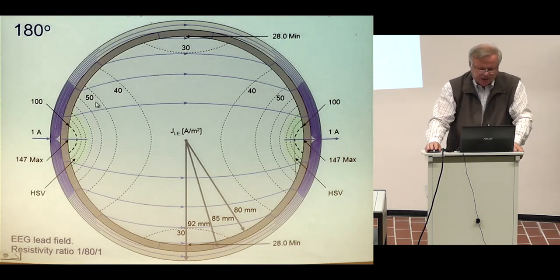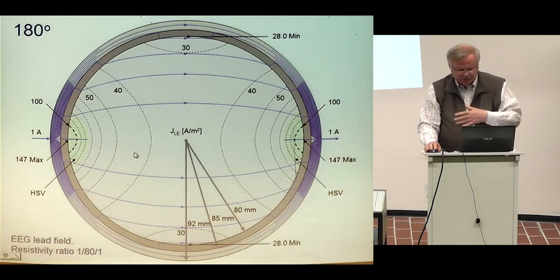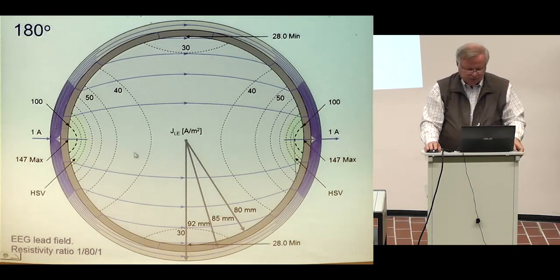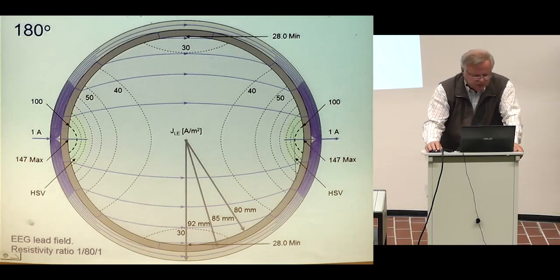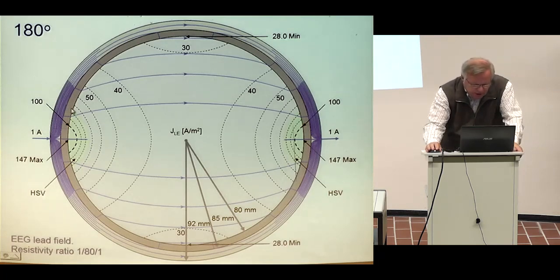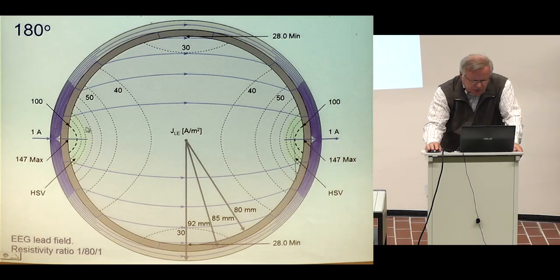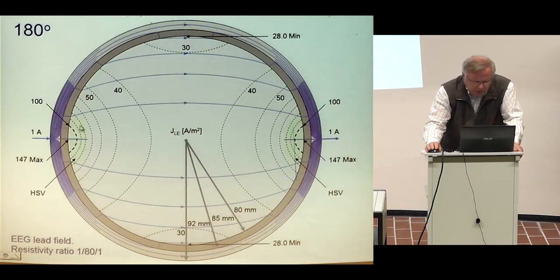The isosensitivity surfaces — which are iso-current-density surfaces — indicate the direction and absolute value of the measurement sensitivity. In addition, we calculated the concept of the Half Sensitivity Volume (HSV). We calculate where the surface is located where the magnitude of the measurement sensitivity is one half of the maximum. We shade with green color this region bounded by this half sensitivity surface.